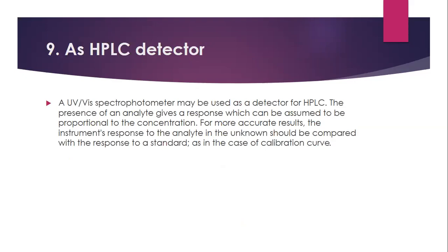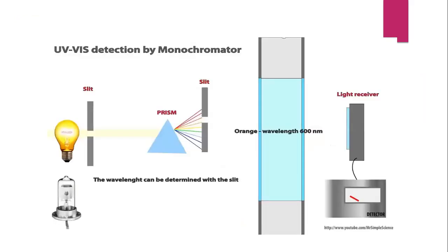The next application is the HPLC detector. A UV visible spectrophotometer may be used as a detector for HPLC. The presence of an analyte gives a response that can be assumed proportional to the concentration. For more accurate results, the instrument's response to the analyte should be compared with the response to a standard, as in the case of a calibration curve. This is shown in the visual representation of UV-visible detection for HPLC.